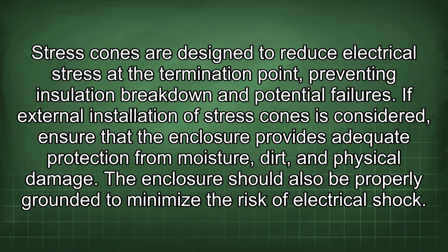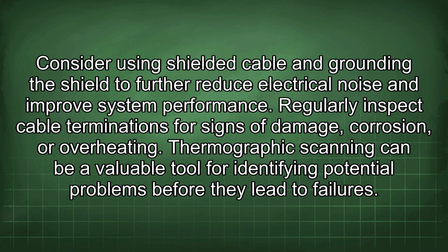Stress cones are designed to reduce electrical stress at the termination point, preventing insulation breakdown and potential failures. If external installation of stress cones is considered, ensure that the enclosure provides adequate protection from moisture, dirt, and physical damage. The enclosure should also be properly grounded to minimize the risk of electrical shock. Consider using shielded cable and grounding the shield to further reduce electrical noise and improve system performance.